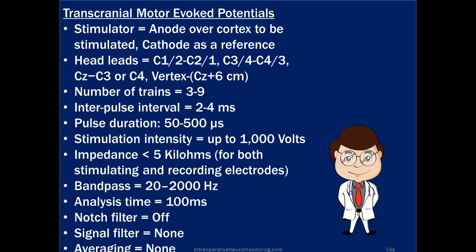Pulse duration, 50 to 500 microseconds. Some equipment regulates you and only allows you 50 or 75 microseconds. Like we said with the pulse duration, the reason why is the longer the duration, the higher the probability of burns. Stimulation intensity, you can go up to a thousand volts.